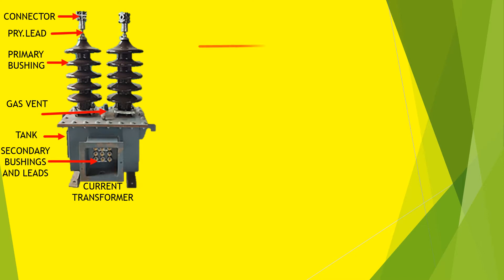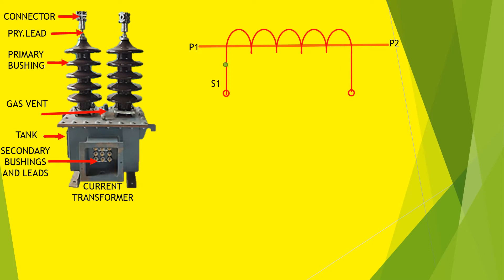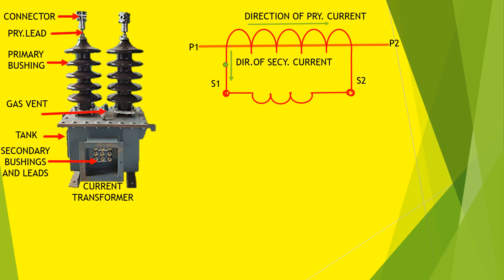Looking at the drawings, P1 and P2 are the connection leads of the primary winding. S1 and S2 are the connecting leads of the secondary winding. If the direction of flow of current in the primary winding is along P1 to P2, then the direction of flow of current in the secondary winding is opposite to that of the primary. A CT is only operated under short circuit condition.